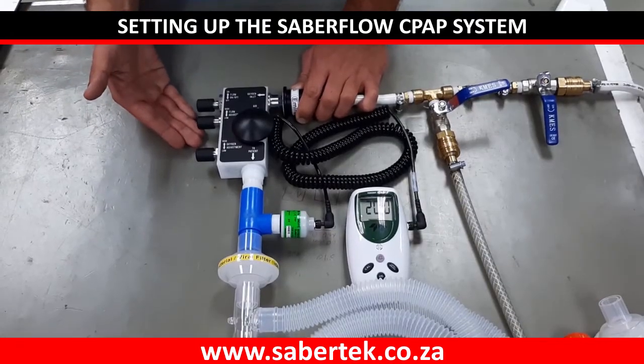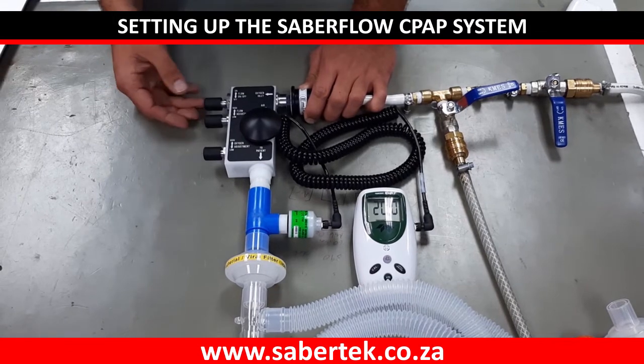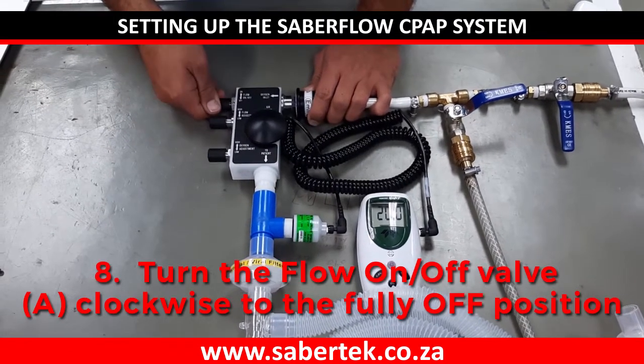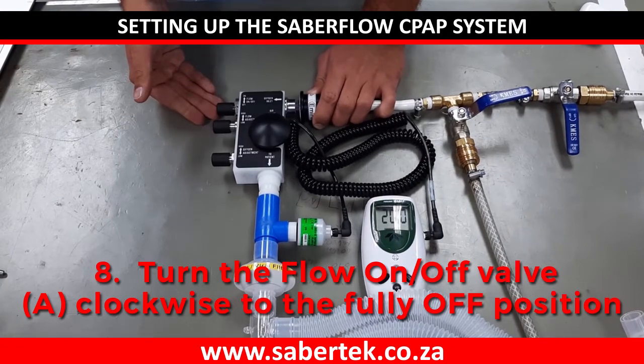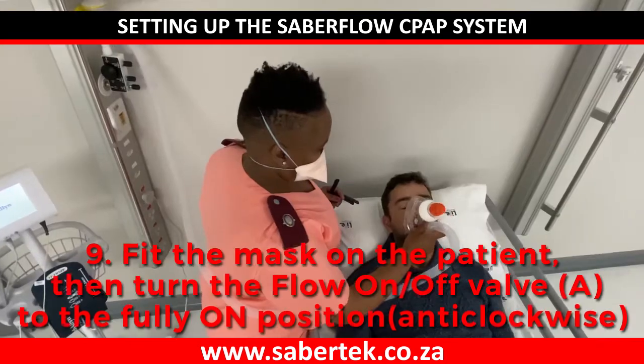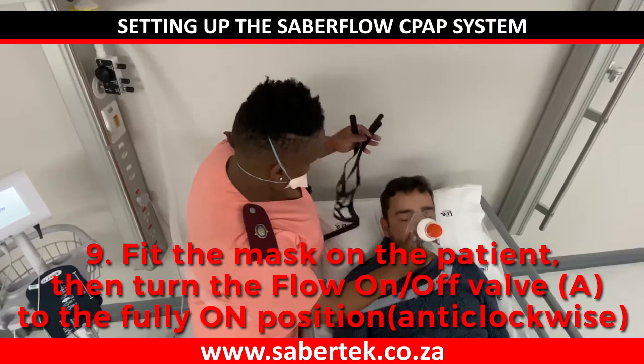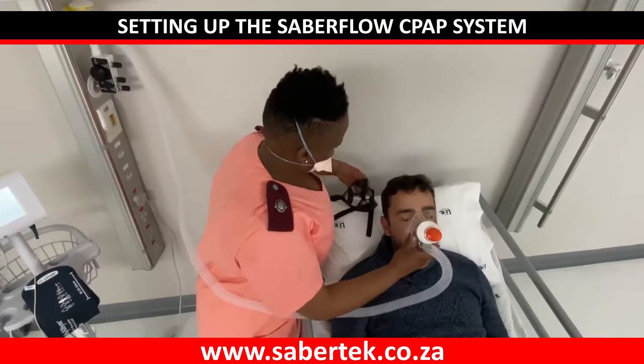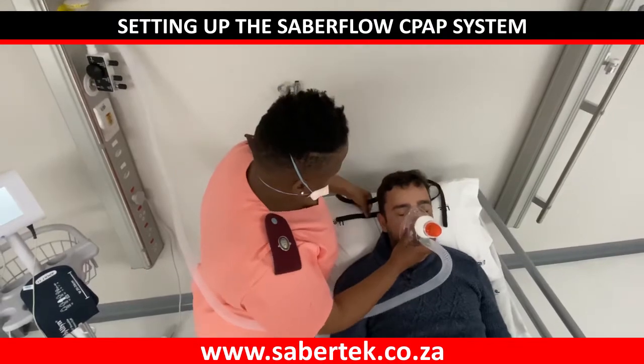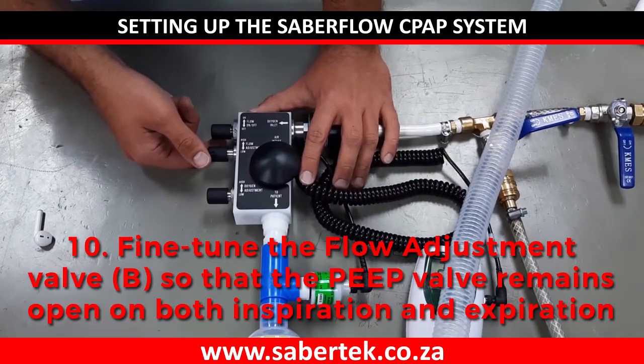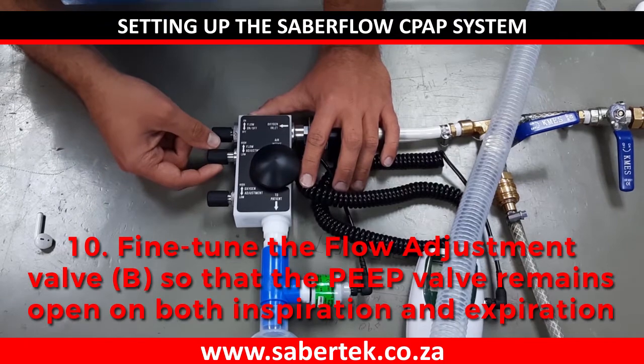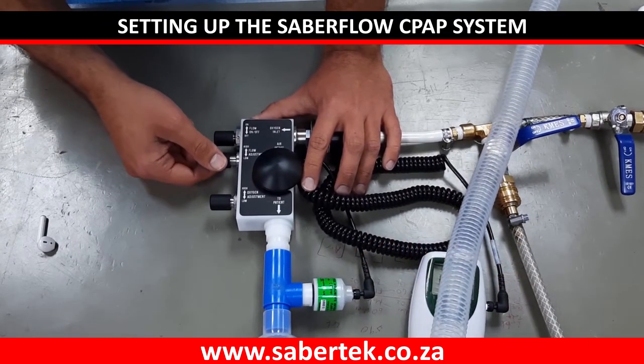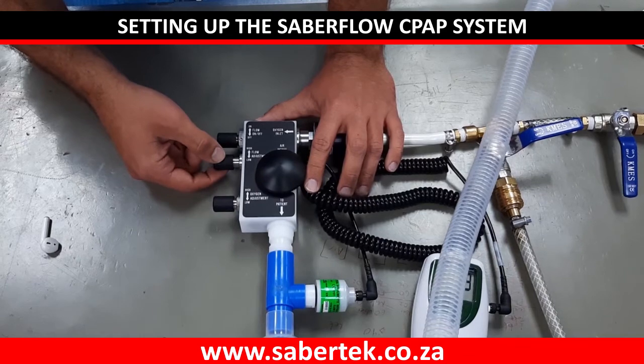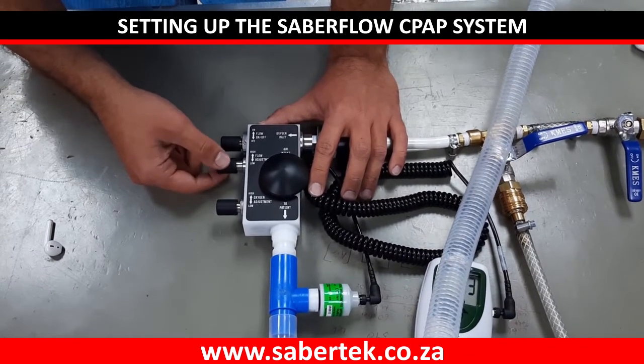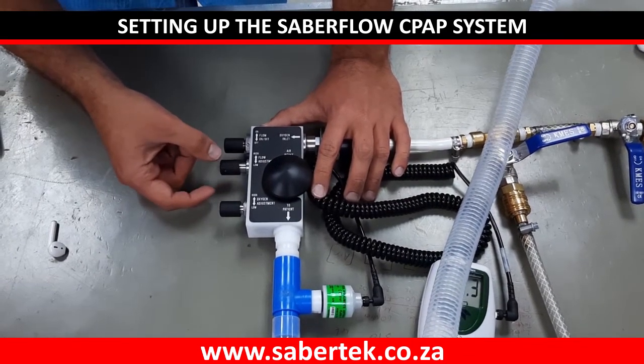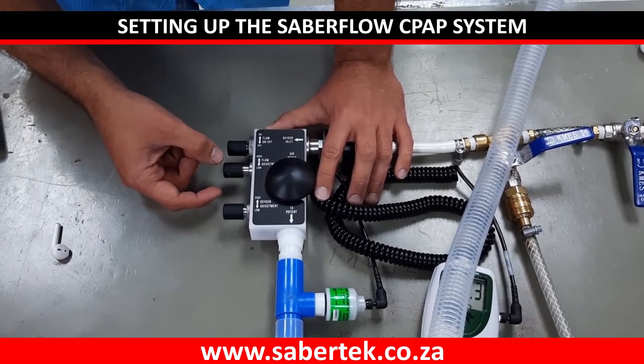8. Leaving the oxygen adjustment C and flow adjustment B set, turn the flow on-off valve A clockwise to the fully off position. 9. Fit the mask on the patient, then turn the flow on-off valve A to the fully on position, anti-clockwise. 10. Fine-tune the flow adjustment valve B so that the PEEP valve remains open on both inspiration and expiration. To check this, feel the exit of the PEEP valve and ensure that a small amount of air is flowing during inspiration. The CPAP device is now ready for use.